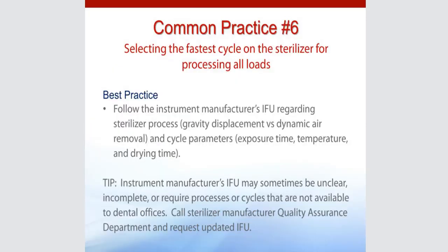Common practice number 6, selecting the fastest cycle on the sterilizer for processing all the loads. This is sort of what I was talking about of the misuse with the immediate use steam sterilization, that you're doing your instruments unwrapped, and I mean, I even had an office who said we unwrap them, but then we put them into pouches before we deliver them.